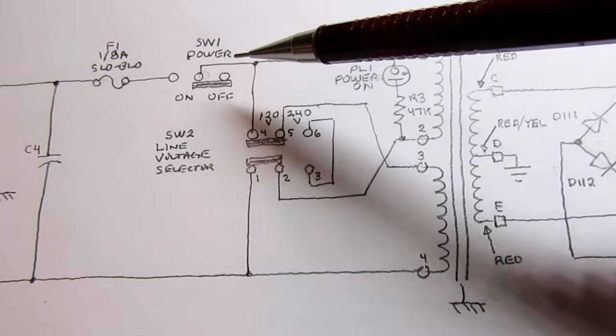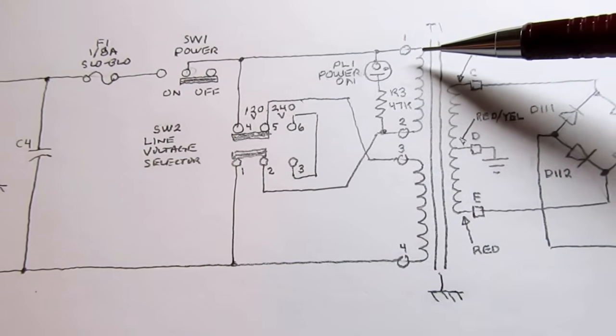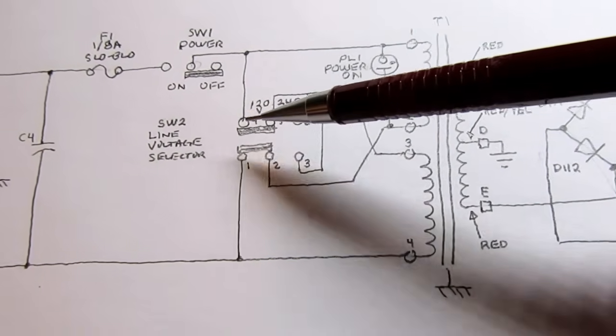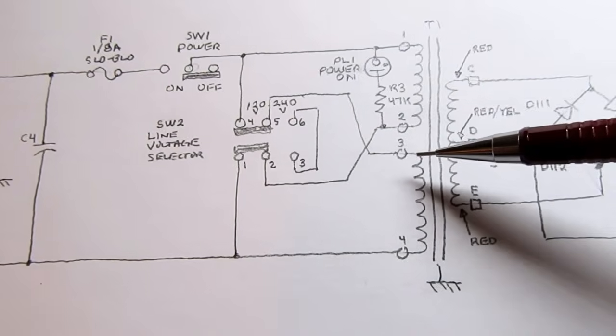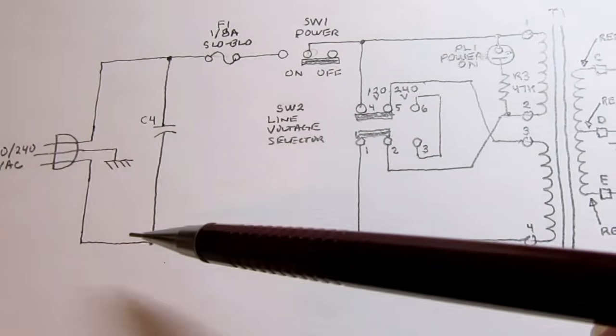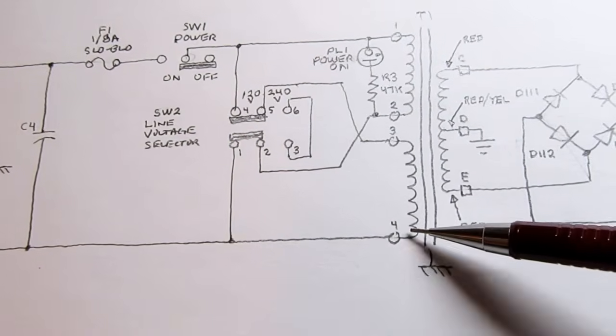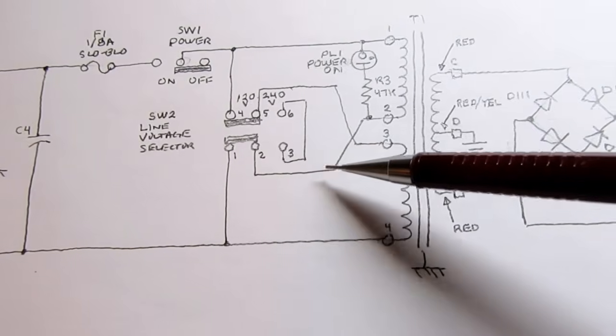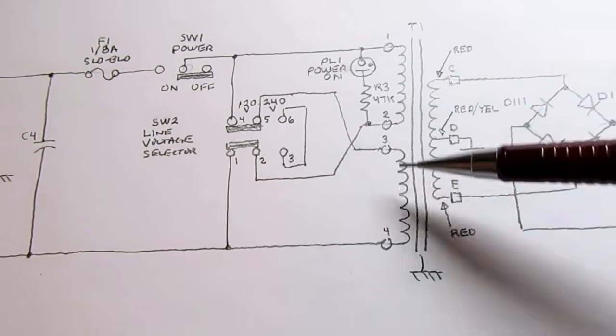So the hot comes in here and it goes to the top of this coil. It also goes through this switch and to the top of this coil. The neutral comes to the bottom of this coil and through the switch to the bottom of this coil, so they're wired in parallel.